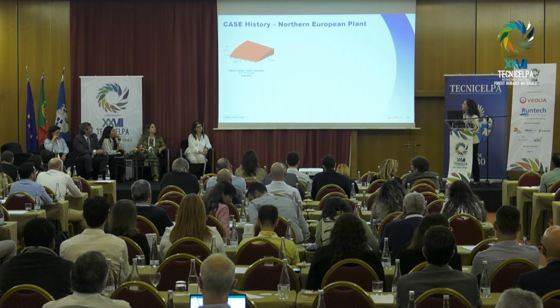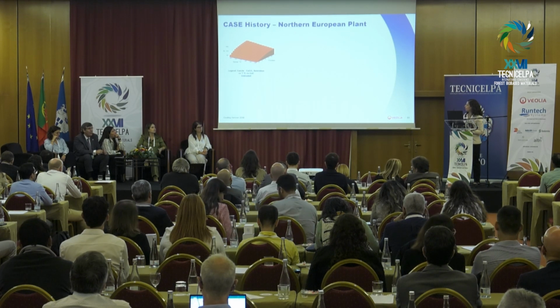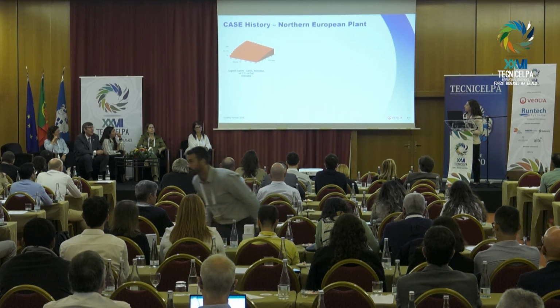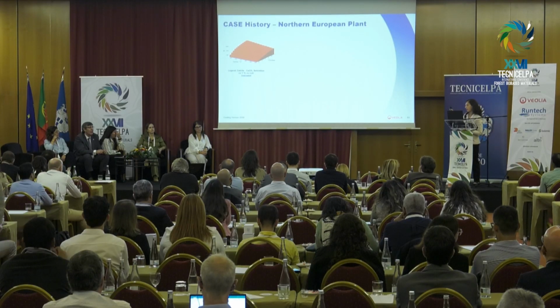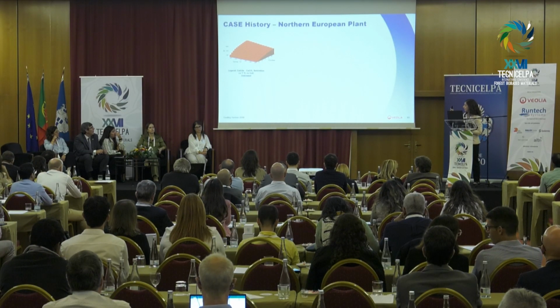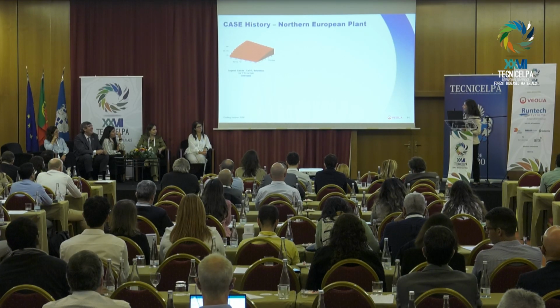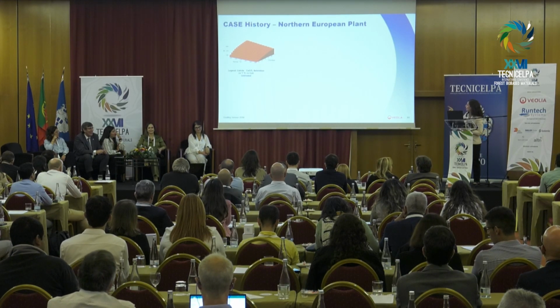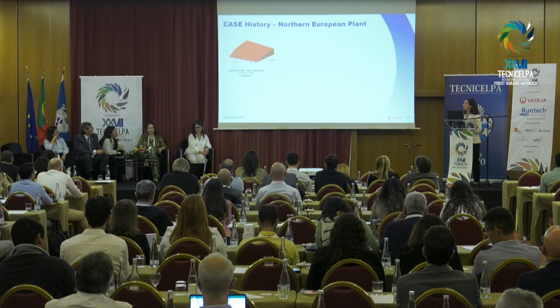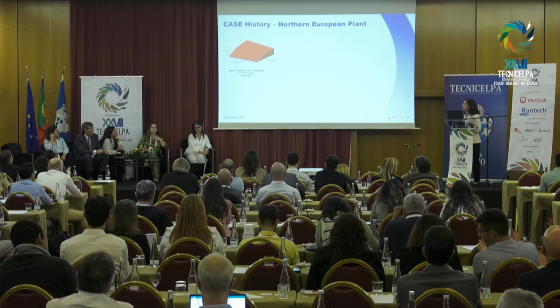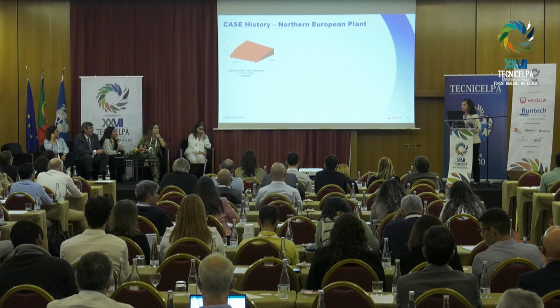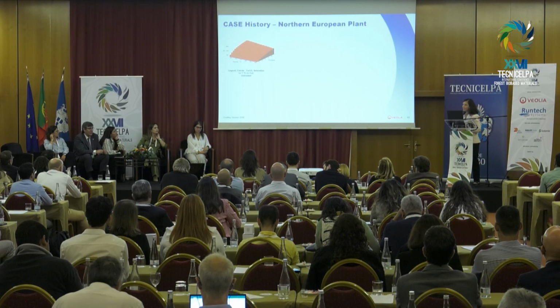In this graph, you can see the evolution of the temperature with the saturation of calcite, calcium carbonate, with the concentration cycles on the cooling tower. With no treatment, it's completely a risk to even put this water in the system, because it will scale the whole system.